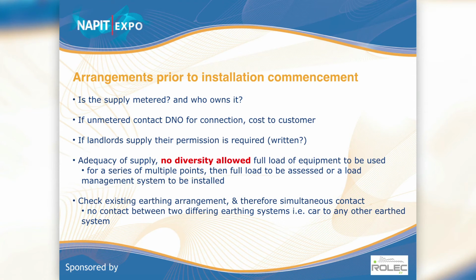Landlords need to give their permission. There is no diversity allowable on this piece of kit. If you've got a 32 amp mode 3 controller, then that is 32 amps that electrical supply will be taking. No diversity. It's just straight on it. And you need to check the earthing arrangement. Usually when we install these, we will be installing these to a TNCS system, a PME system, today's modern earthing system. And the problem is when they go out of the envelope of the building and you're out of the equipotential zone, you leave yourself open to unfortunate happenings if we lose the neutral.